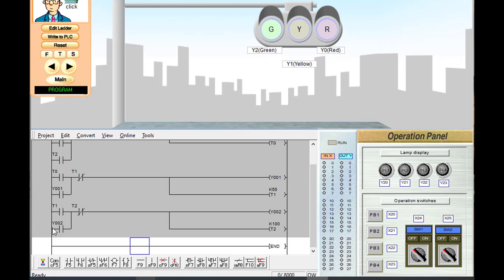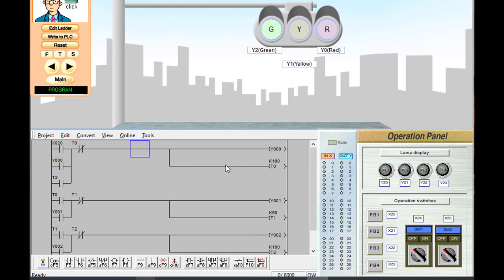To summarize: green light is on when T1 comes, Y2 is on and latched by that contact, and timer T2 for 10 seconds starts. After 10 seconds T2 is on, so Y2 turns off — green light off — and simultaneously Y0 turns on again. The timers then cycle: 10 seconds for red, 5 seconds for yellow, then 10 seconds for green, and T2 restarts the first line instead of requiring a push button press.